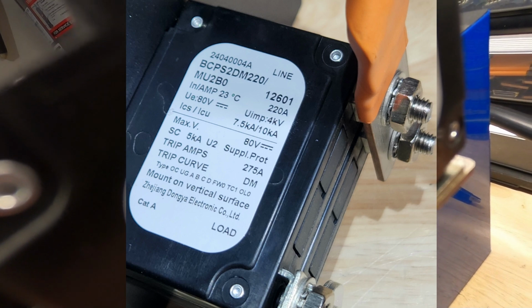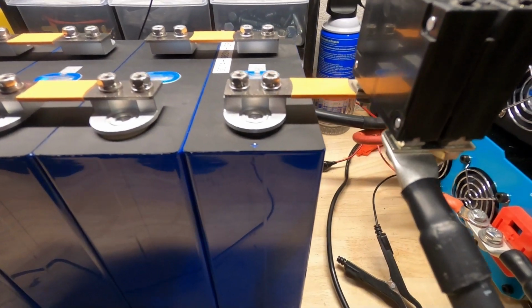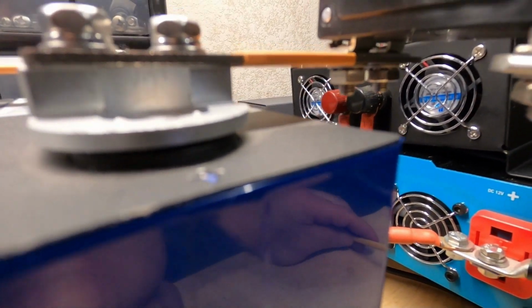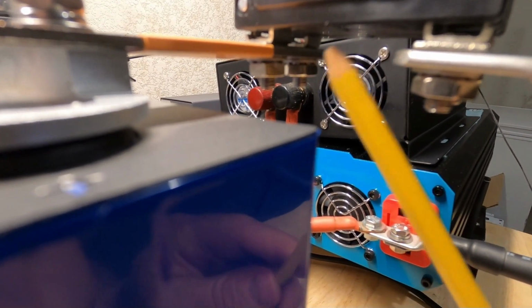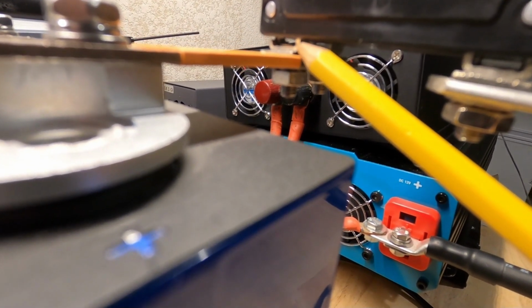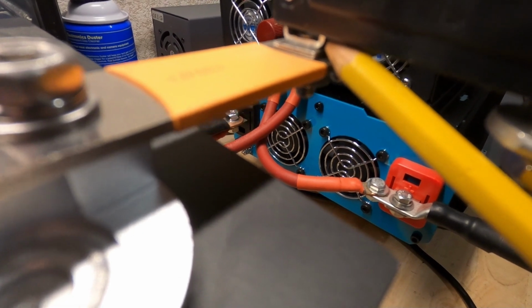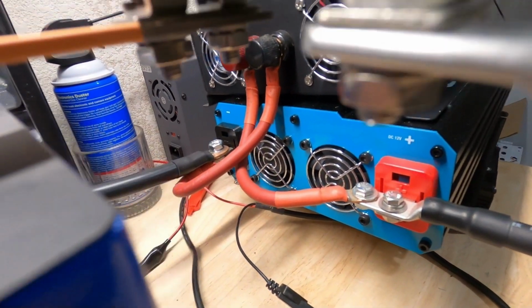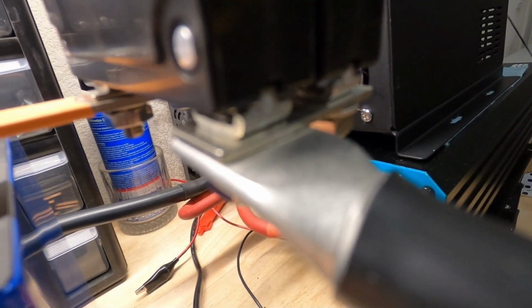Okay, so looking at the breaker, you'll notice that this is a 220 amp breaker, continuous rated. And on the side there it says 275 amp trip. So that's what is required to trip the breaker, it's 275 amps. Now, if you look closely, you'll see this little bridge piece, this little metal bar. See that sitting underneath the terminals of the breaker? It actually has it on both sides here. You can see it there.